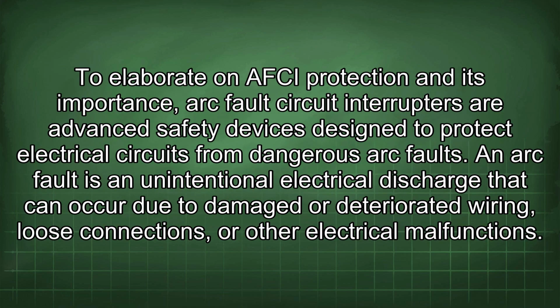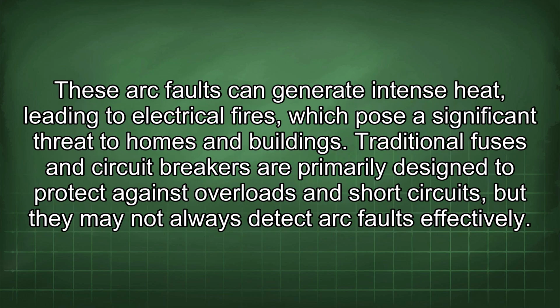To elaborate on AFCI protection and its importance, arc fault circuit interrupters are advanced safety devices designed to protect electrical circuits from dangerous arc faults. An arc fault is an unintentional electrical discharge that can occur due to damaged or deteriorated wiring, loose connections, or other electrical malfunctions. These arc faults can generate intense heat, leading to electrical fires, which pose a significant threat to homes and buildings. Traditional fuses and circuit breakers are primarily designed to protect against overloads and short circuits, but they may not always detect arc faults effectively.